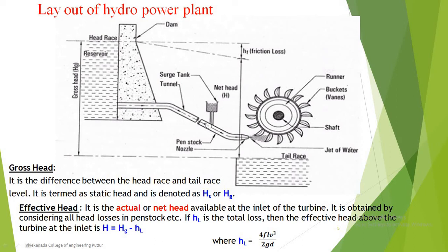When the gate valve is closed, the water will flow in the opposite direction with high velocity. It will impact on the sides of the penstock, even on the gate. This is called water hammer. To reduce this effect, the surge tanks are constructed.